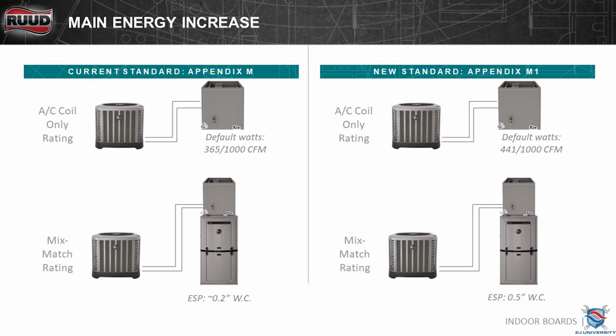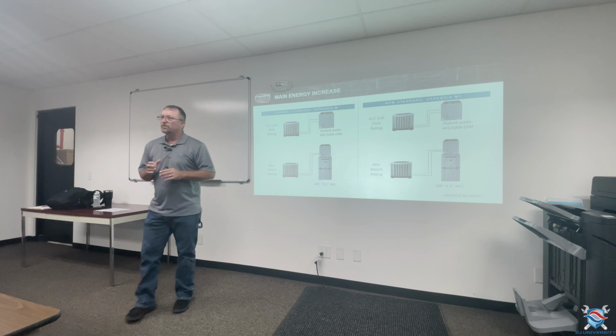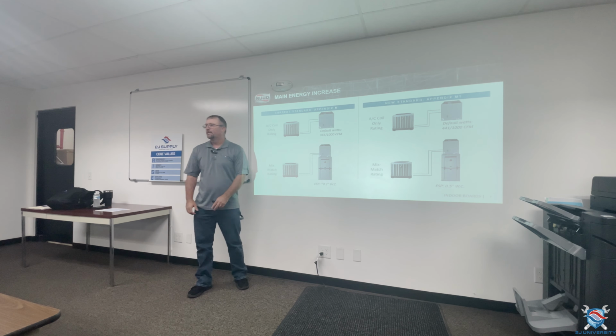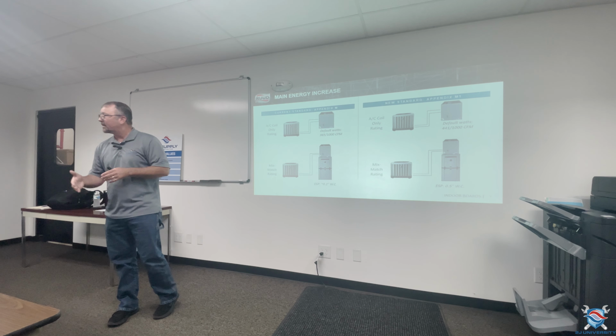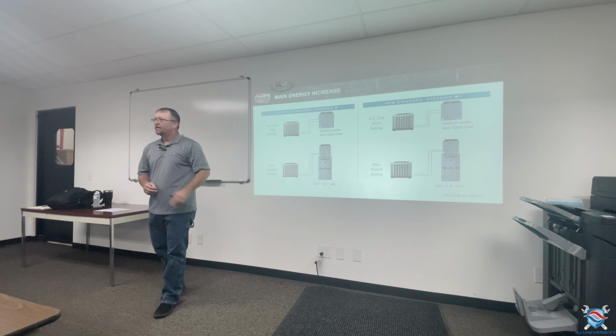Kind of the difference between SEER and SEER 2. What they have done basically is they have taken, over here we have our old M or SEER rating. All units were rated at 365 watts at 1000 CFM at a 0.2 static. What they've done is they've taken that rating and they've changed it for more real life situations. So how many times in a home do you really see 0.2 static?